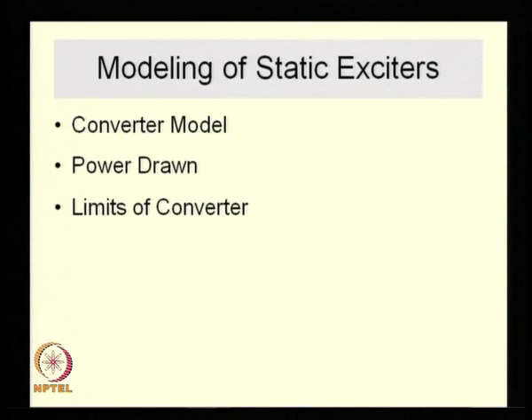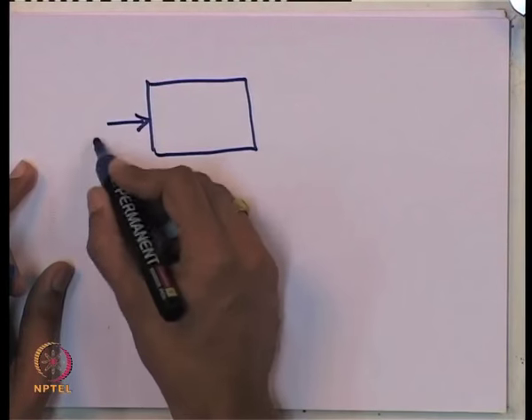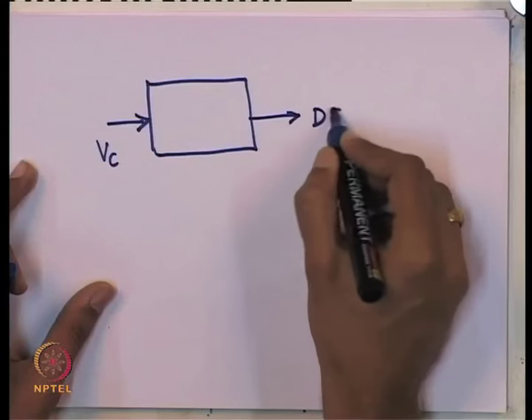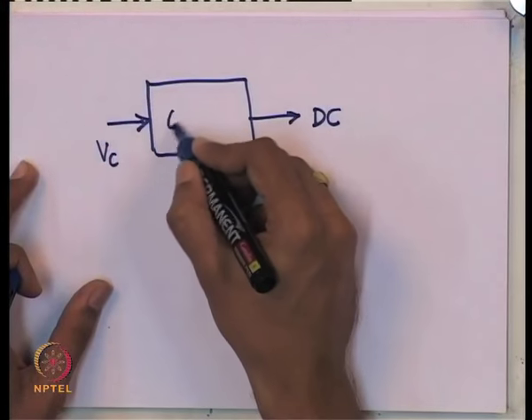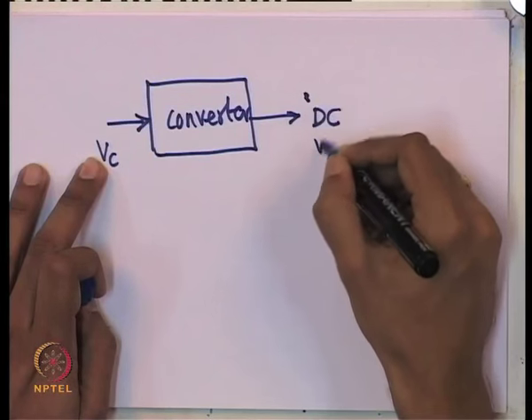This presumes that we are doing power system studies and do not require detailed modeling of the converter. For excitation system design itself, of course, you would need to model the converter in more detail. For a static excitation system, the converter can be modeled as a static block: if I give a control signal V_C, the DC output of the system immediately changes. The field voltage is algebraically related to the control signal.